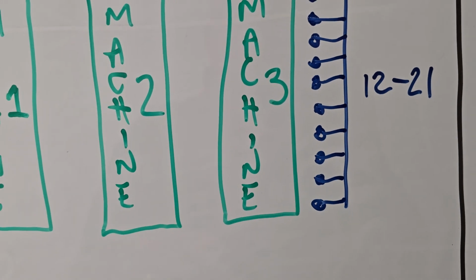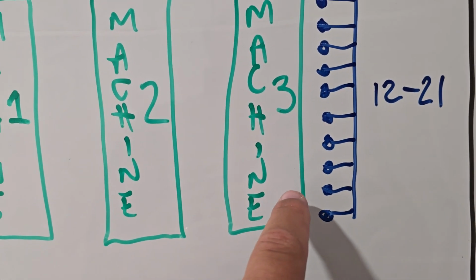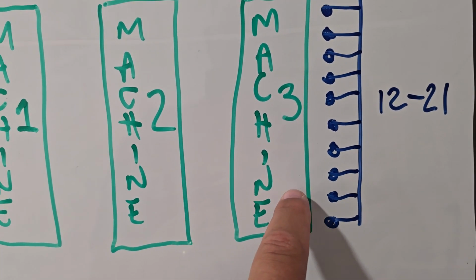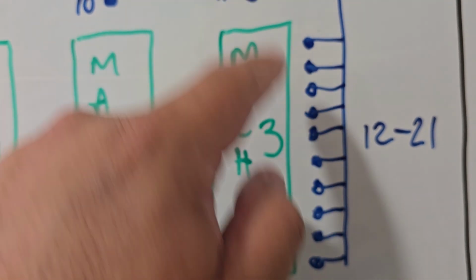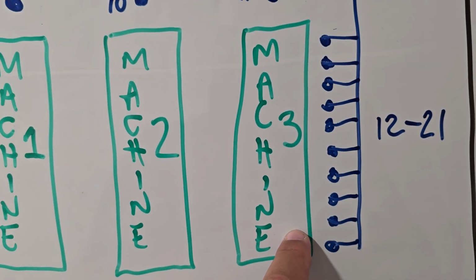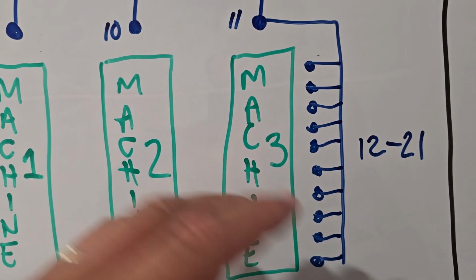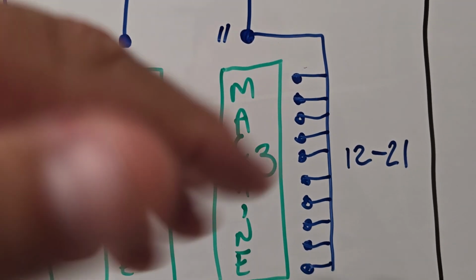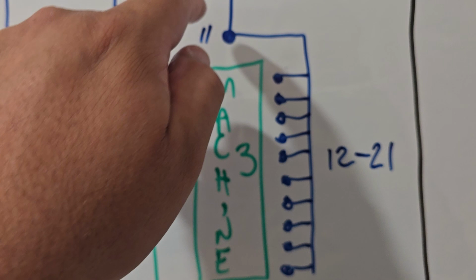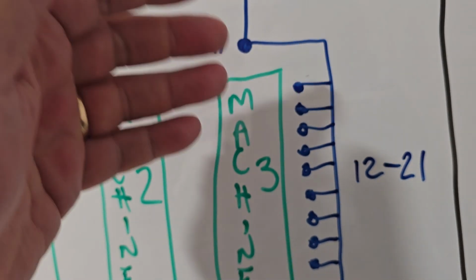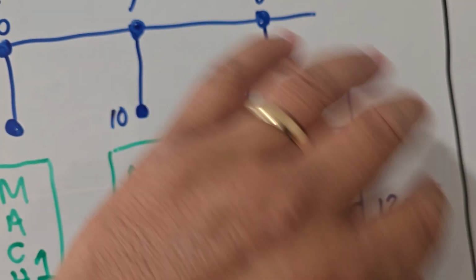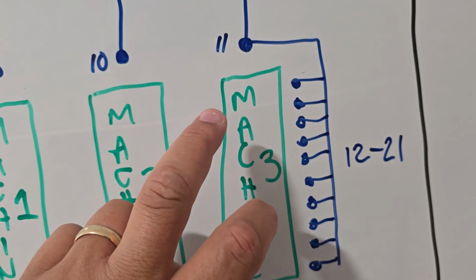It's important to note that we have to understand if this machine can change speeds and the impact on compressed air utilization if that machine operates at different speeds. If it just operates at one speed, then it's much easier to use process tools like receiver tanks, regulators, amplifiers, all the stuff that we can use right here, filtration, drying, to give the air that's required right here.